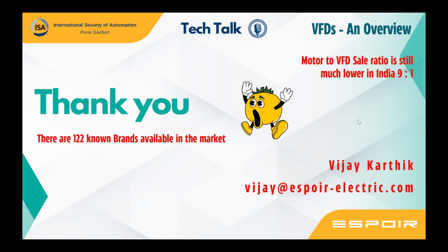And there is one more question, on 18 pulse VFD. Sir, 6 pulse and 12 pulse are common in LV drives, and very few brands have 12 pulse. For 18 pulse you need a different transformer. In medium voltage applications, 18 pulse, 24 pulse and 36 pulse are quite common. I can explain what kind of design you need to address that. You need a very special design, where every section is a 6 pulse section and you need a power input for each.